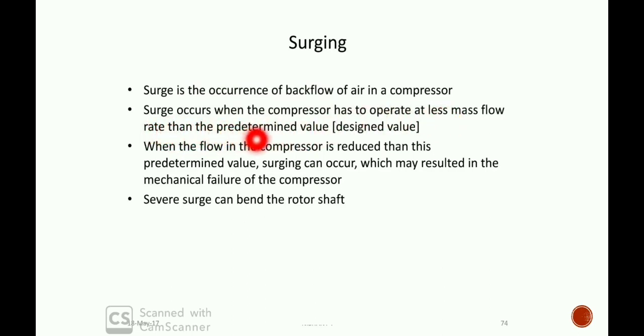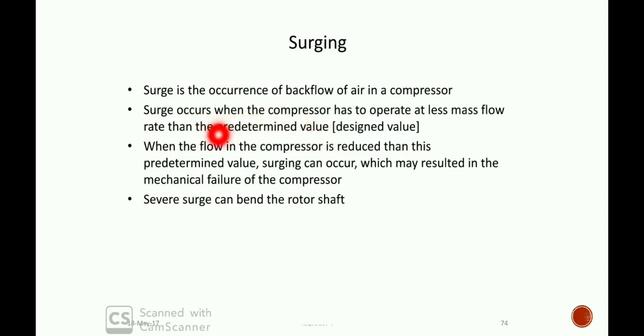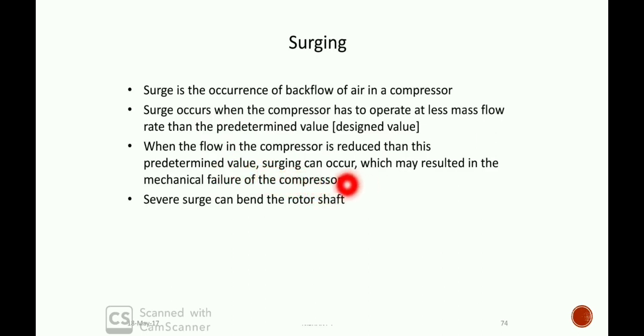This is the design condition of a particular compressor. When the flow in the compressor is reduced below this predetermined value, surging can occur, which may result in the mechanical failure of the compressor.